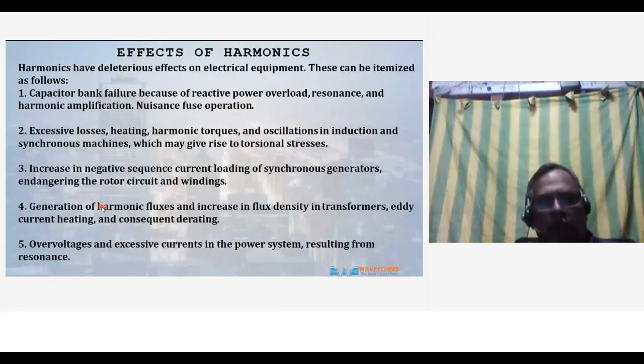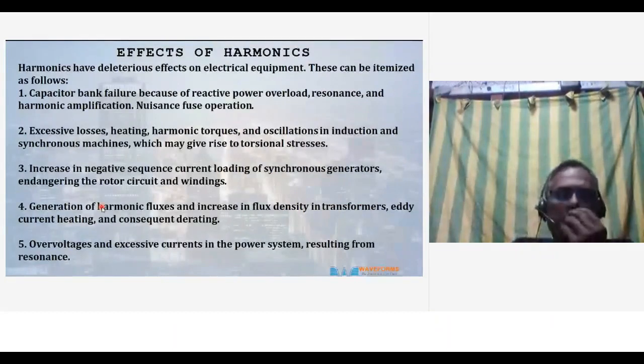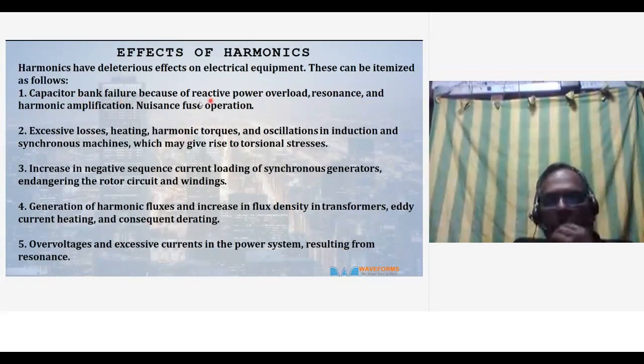So it's important to understand the effects of harmonics. Harmonics have deleterious effects on electrical equipment. They can be itemized as follows: capacitor bank failure because of reactive power overload, resonance, and harmonic amplification. Normally, a capacitor bank acts like a harmonic sink, and they react with the network. So that is the big issue. Excessive losses, pulsating harmonic torques and oscillations in induction and synchronous machines that may give rise to torsional stresses.